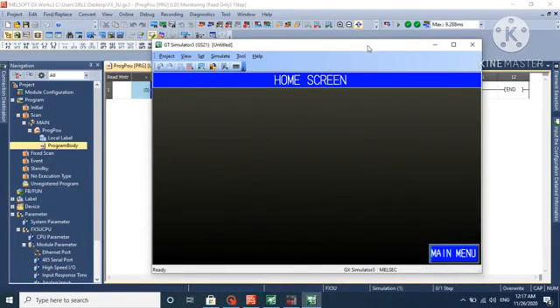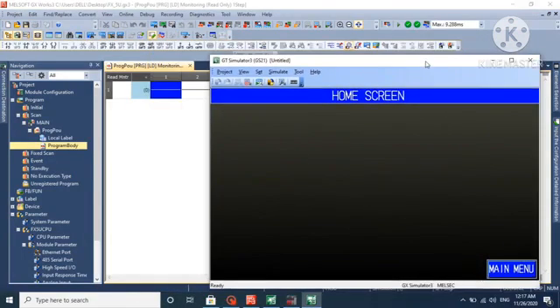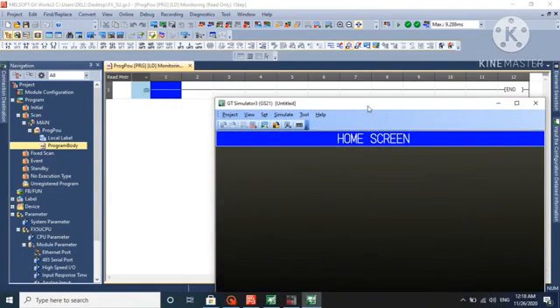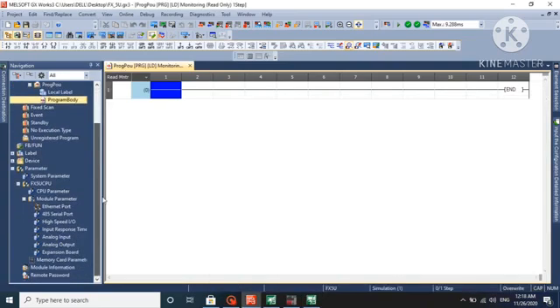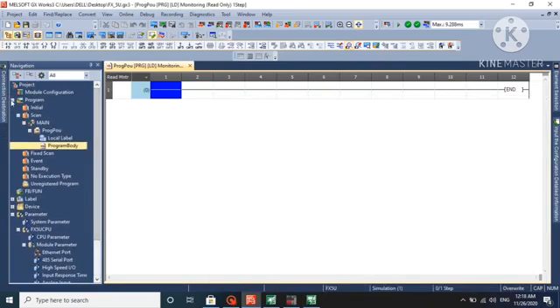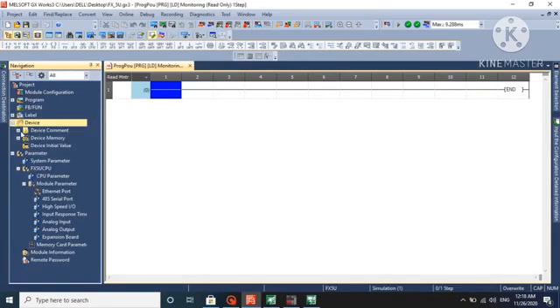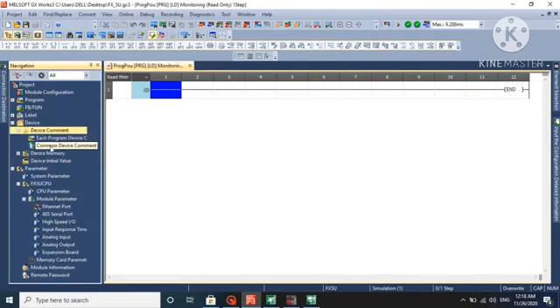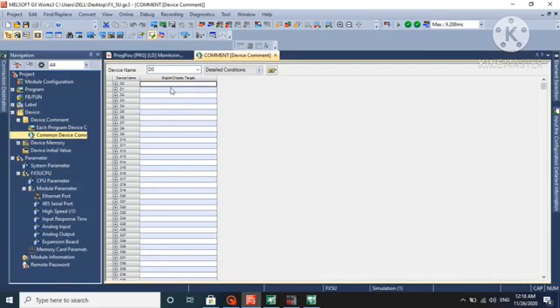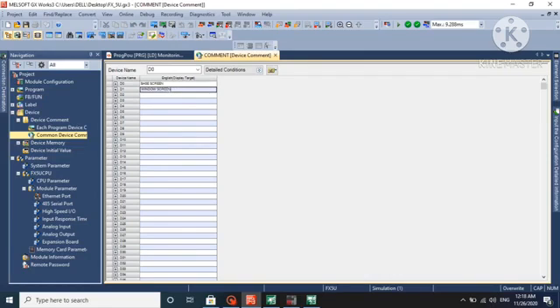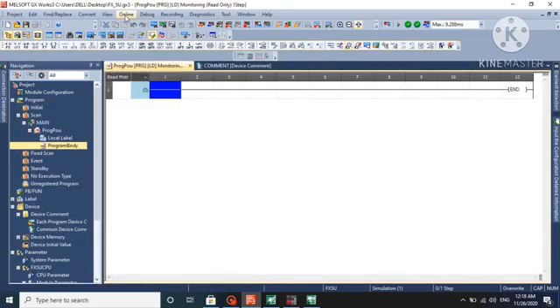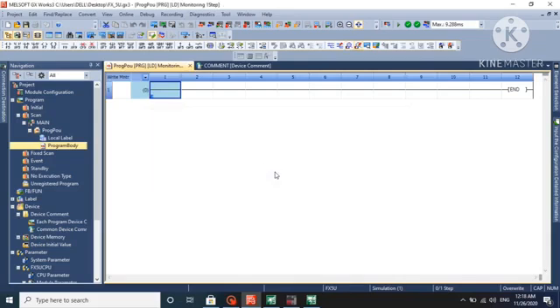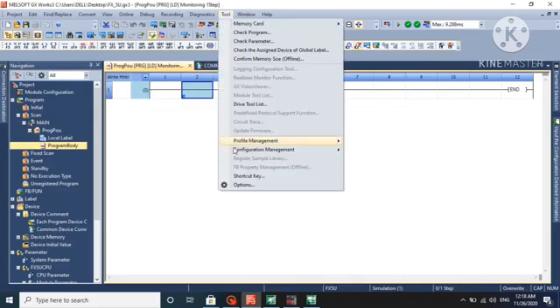We'll write a little logic inside the PLC in ladder format to demonstrate how this pop-up screen works. In device settings, we have already mentioned D0 and D1. D0 is for base screen and D1 is for window screen. We'll go to write mode so we can online change the program.